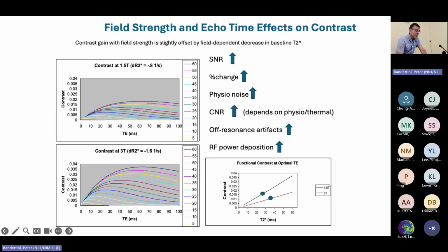This tries to illustrate this point. If you're in an area where the signal is dropped out, where there's a big hole in the brain because of a shimming problem, and you try imaging there, you don't want to be at a TE of 30 milliseconds, you want to be at a TE of 10.